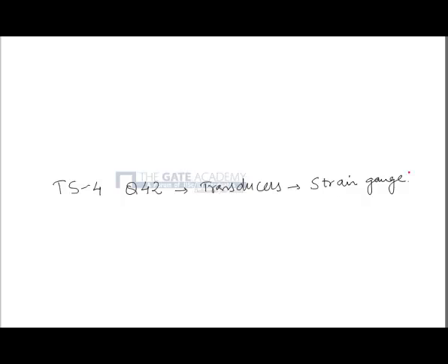A strain gauge bridge shown in the given figure has two fixed resistors R1 and R2 of 120 ohm each and a variable resistance R4 which is 120 ohm at zero strain and 120.63 ohm with a strain of E. So when strain is given, the value of resistance will change and it becomes 120.63 ohms. The gauge factor is 2.04. Determine the strain where the gauge is attached.